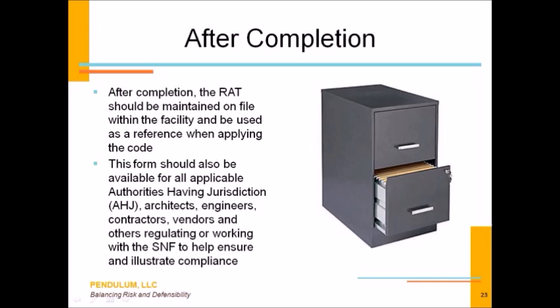You need to do a risk assessment whenever you're doing any renovation, remodeling, new construction, or change of use of any area or space in your healthcare facility. So, for example, if you're going to take an office and translate it from an office space into a patient care area, like an exam room, you need to look at that space and perform a risk assessment on all of the systems and any equipment that will be within that space, and determine if those new elements that will be in that space are going to qualify as a category 1, 2, 3, or 4.